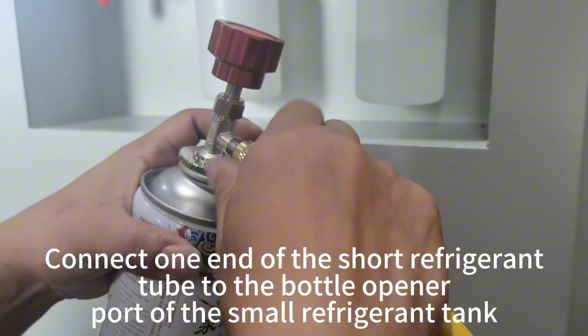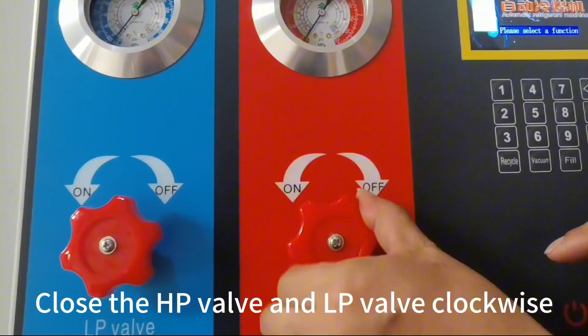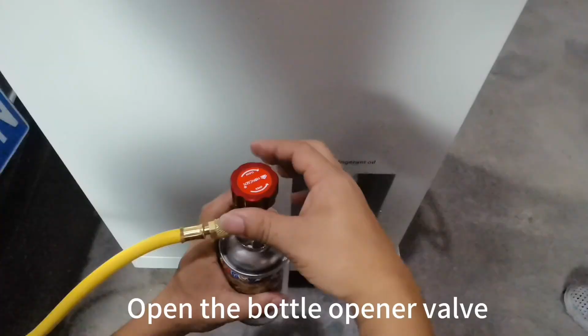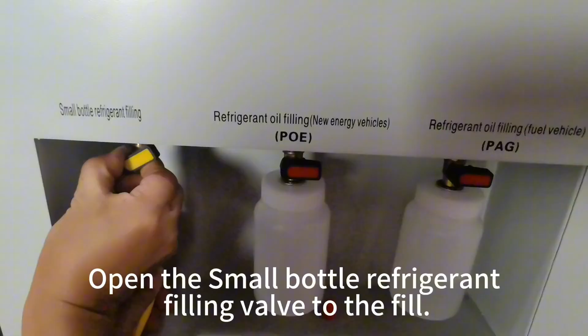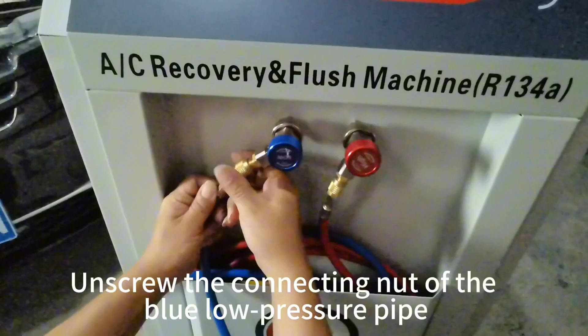Connect one end of the short refrigerant tube to the bottle opener port of the small refrigerant tank. The other end is connected to the small bottle refrigerant filling port. Close the HP valve and LP valve clockwise. Open the bottle opener valve. Press the air button. Open the small bottle refrigerant filling valve to fill, replenishing the refrigerant in the storage tank. Unscrew the connecting nut of the blue low pressure pipe.